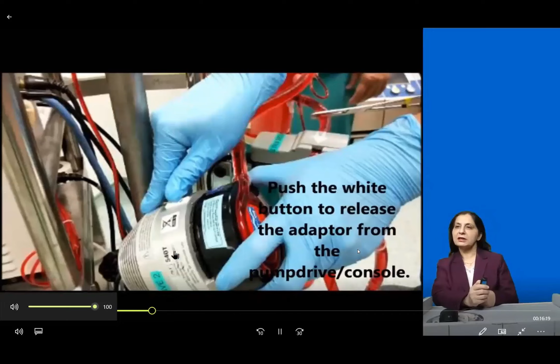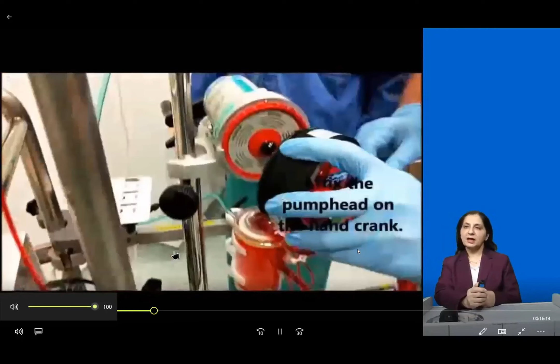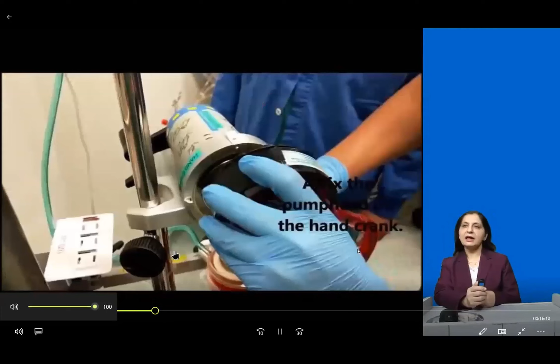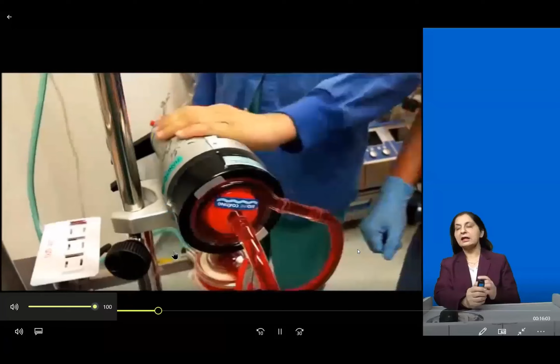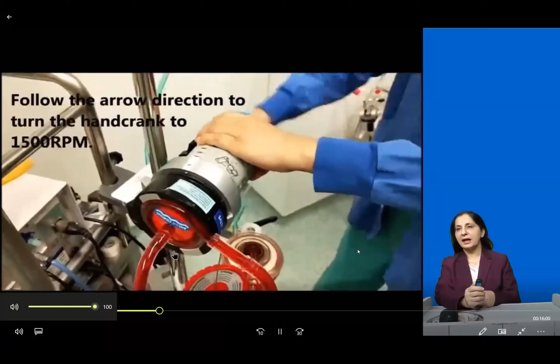You can see that just with the push of the white button to release the adapter from the pump drive, affix the pump head onto the hand crank, again adjusting the white button on the hand crank, and without further delay, once the pump head is on the hand crank, well seated, you follow the arrow direction and start moving the hand crank at a rate of 1500 RPMs and slowly go up.